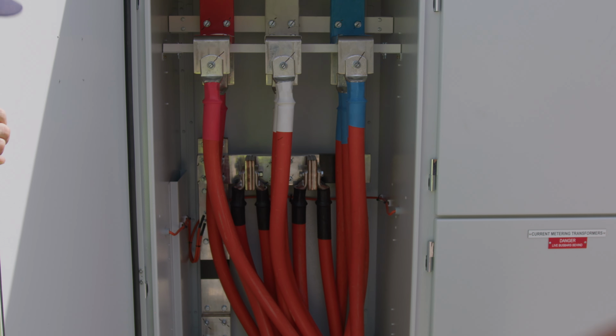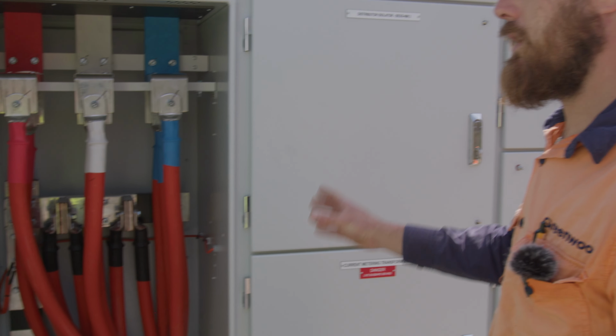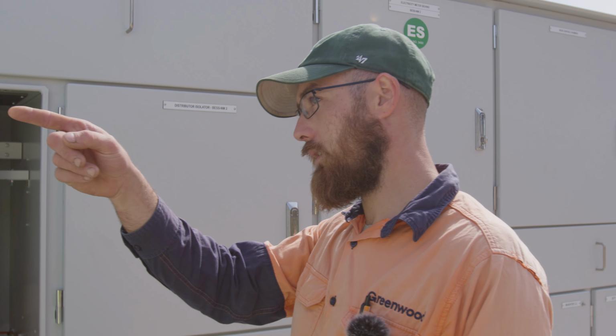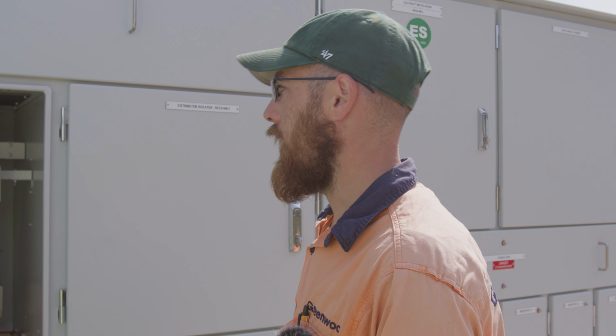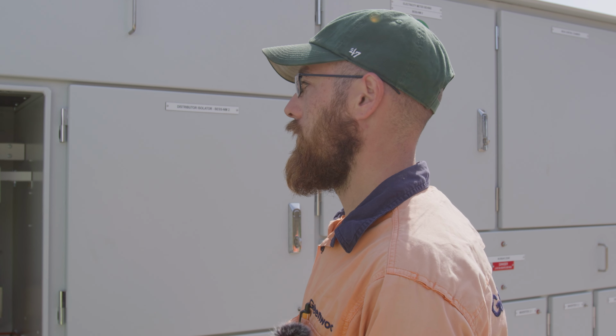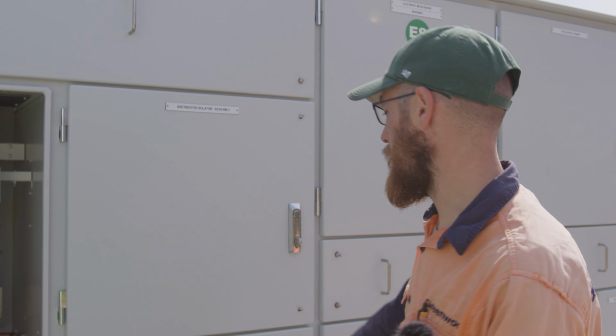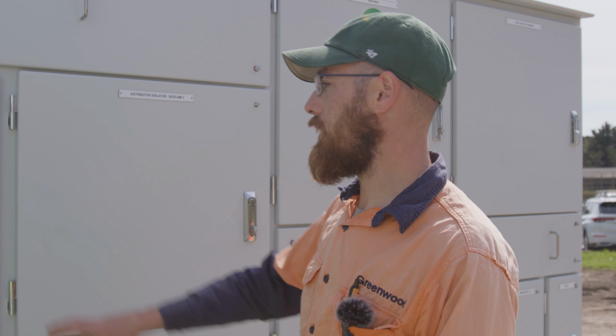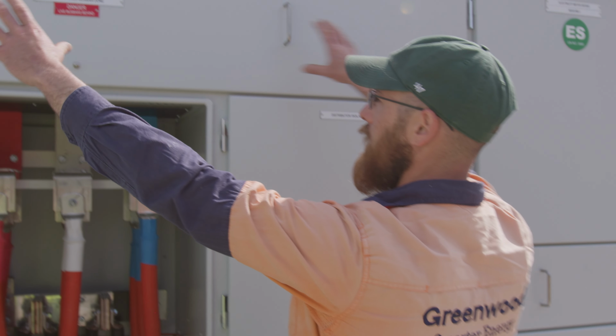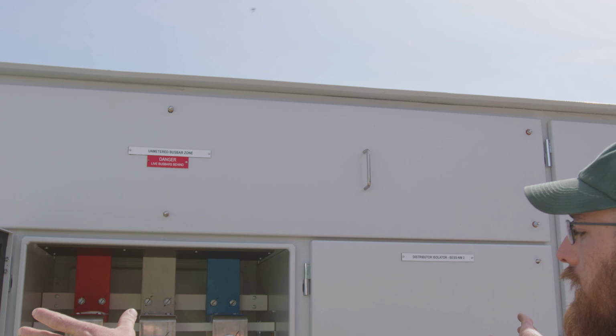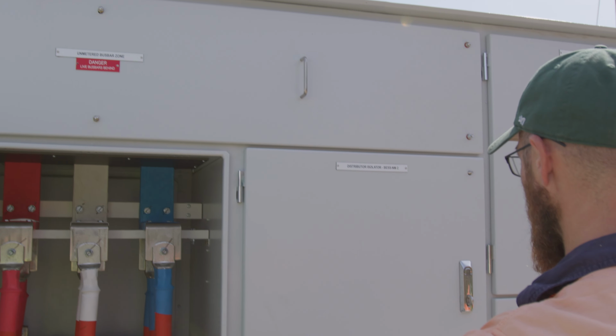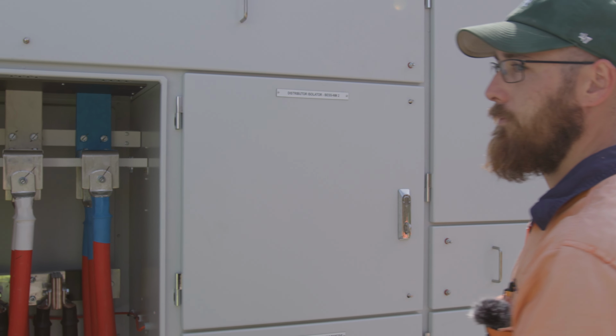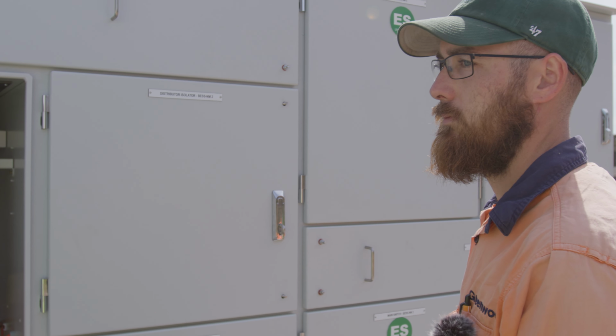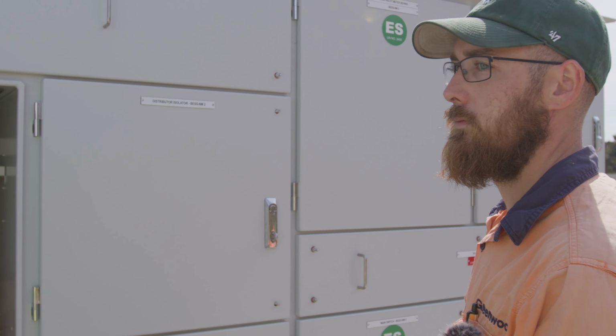So the unique thing about this supply is it will be unmetered from the point of connection at the board down there up into this board. Wow. So point of supply all the way through till the metering transformers, which are here. So this connection will supply the bus bar above. And then we'll come down either side through an isolator, and then down through metering transformers and across to the main switches. Very impressive.